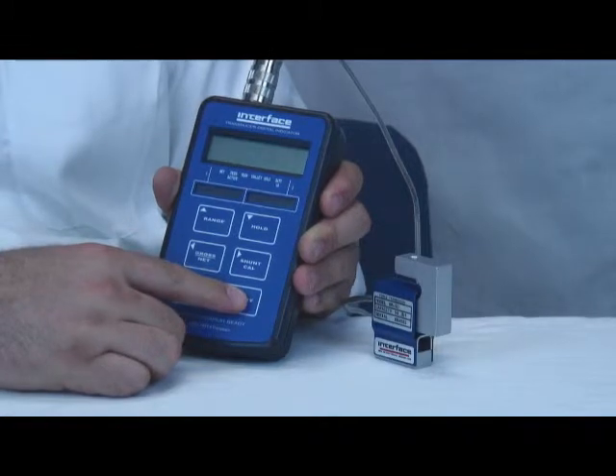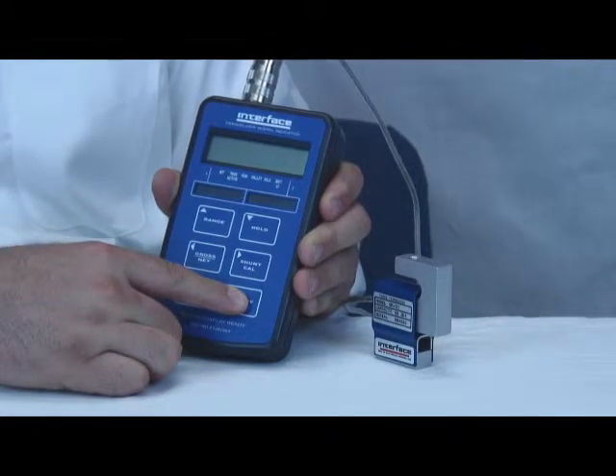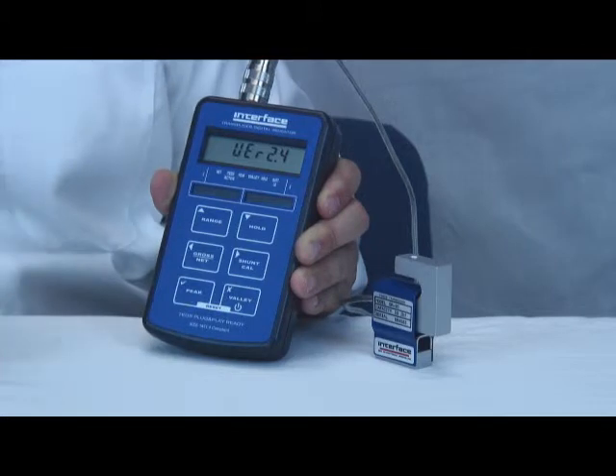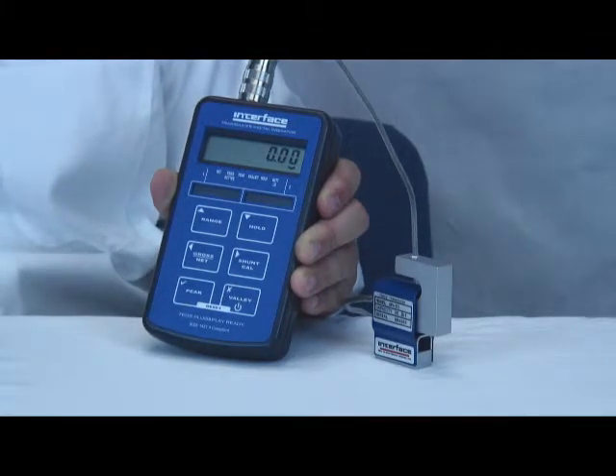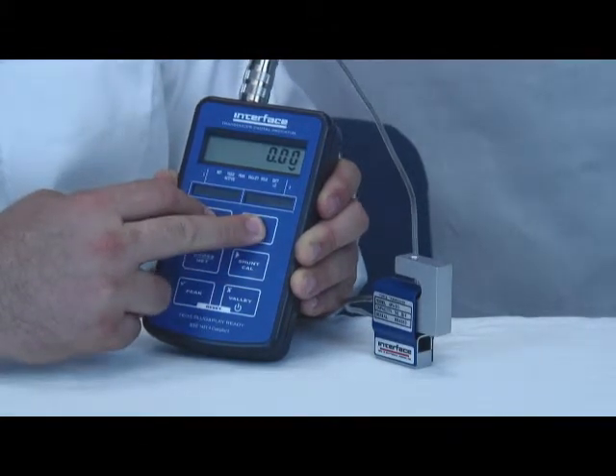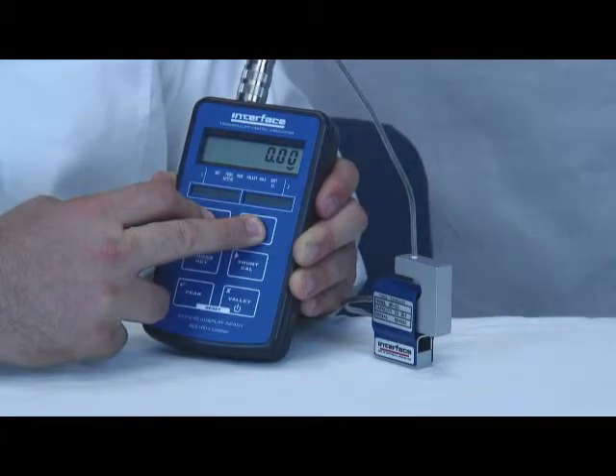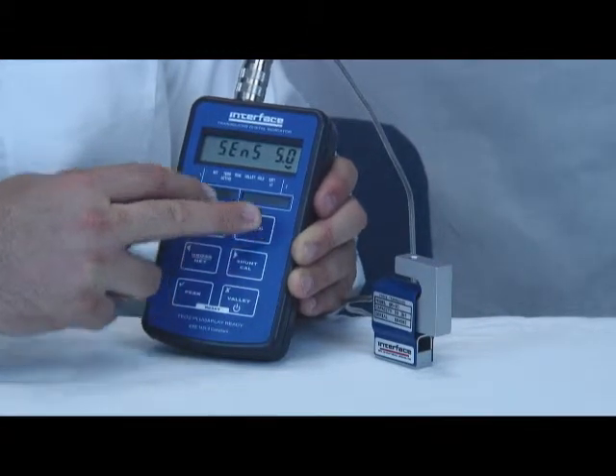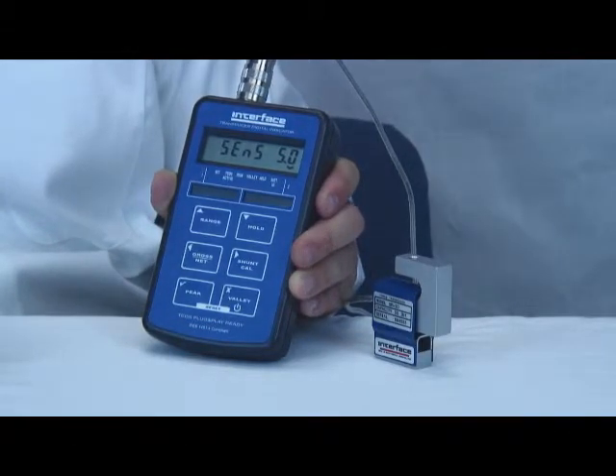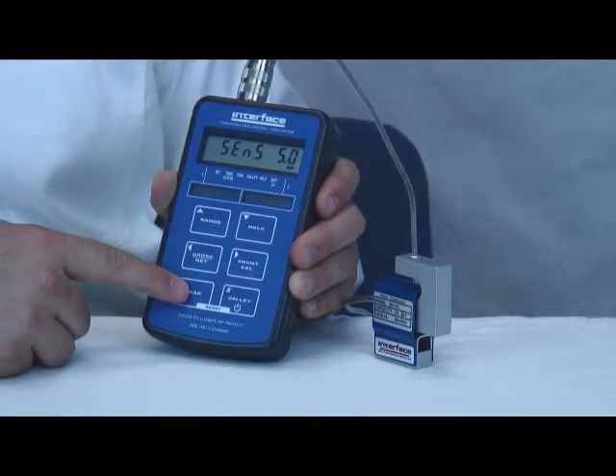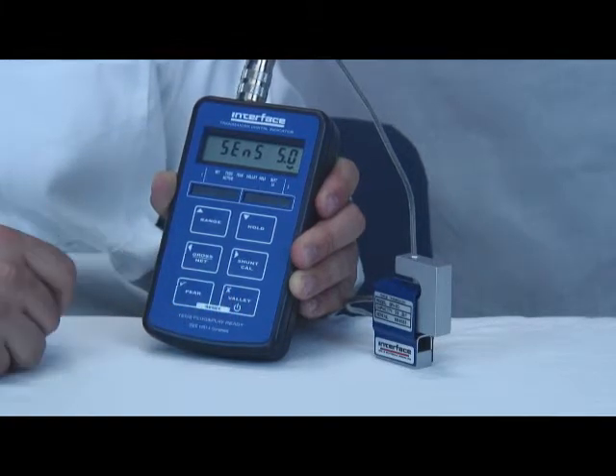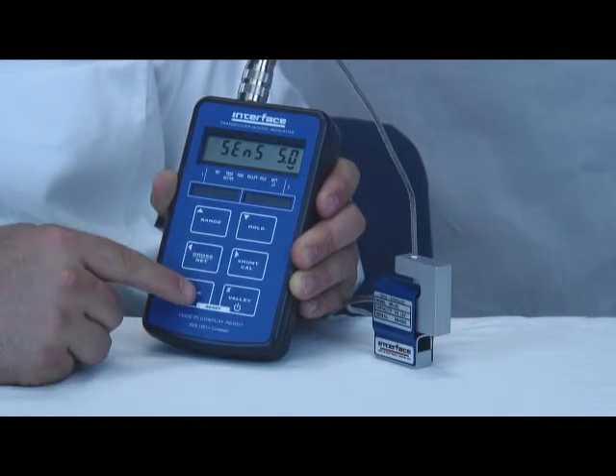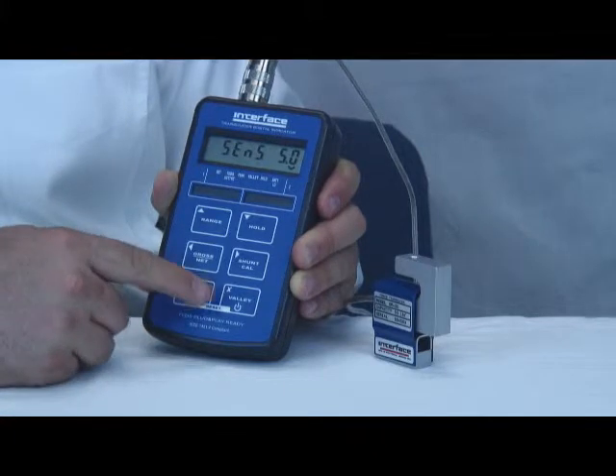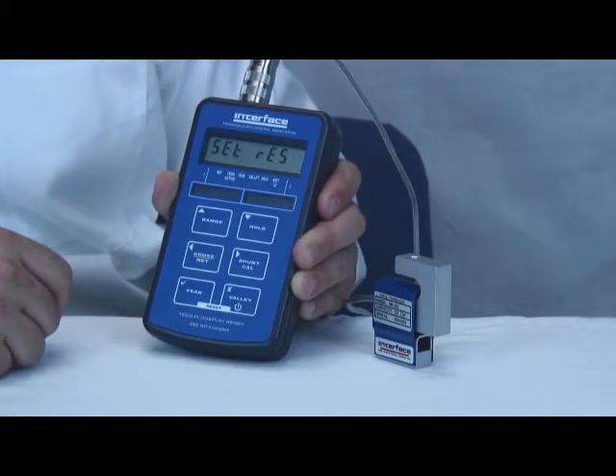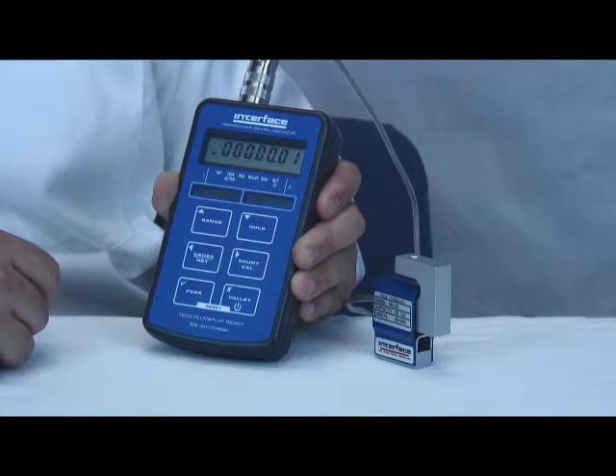First, the 9320 must be powered on by pressing and holding the power button. Once on, the calibration mode is entered by pressing and holding the two upper buttons. Once in the calibration menu, the check button is used to confirm a selection and the X is used to move on. Sensitivity of 5.0 is correct, so we'll skip that. Set resolution. This is a 50-pound load cell and we want 0.01 pound resolution.